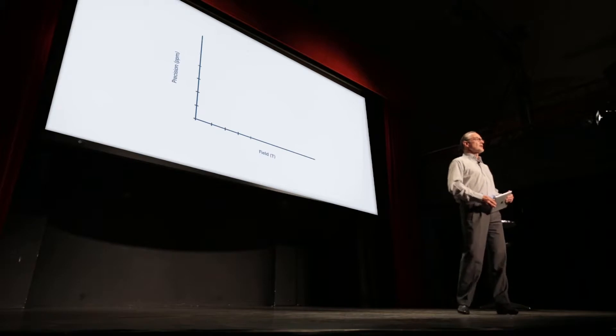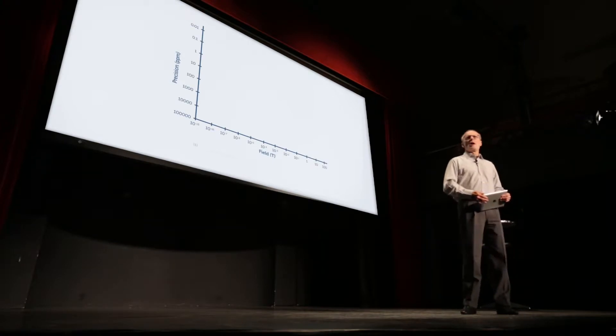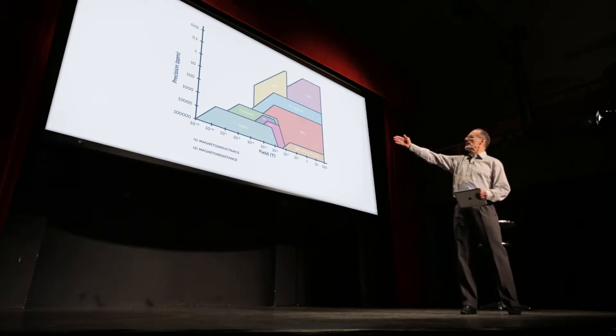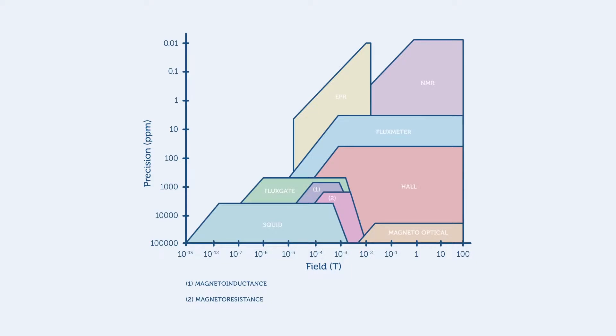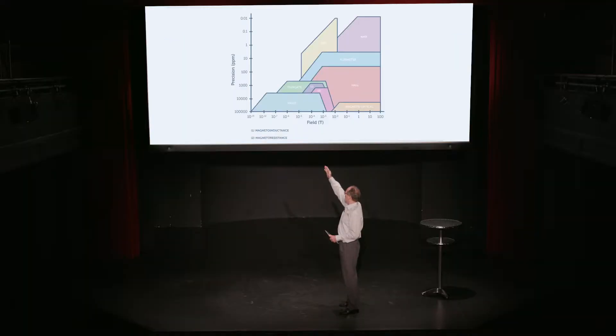When we hear the term magnetometer, or the older term Gauss meter, most of us are thinking about a Hall magnetometer. And it's true that Hall magnetometers occupy a very important place on this diagram where we're categorizing all the different field measurement techniques on the basis of the range that they cover and the precision that they give you.